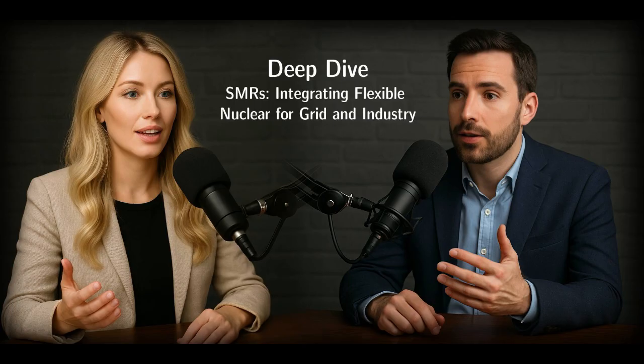Okay, so beyond just following load up and down, how do small modular reactors help with more advanced grid services, like frequency regulation and voltage support? Right, so for frequency regulation, they offer immediate governor response, that's primary frequency response, the instant reaction to a frequency drop, and they can participate fully in secondary response through automatic generation control. How much adjustment can they provide there? Typically a plus or minus 5% power adjustment capability specifically for frequency regulation, with sub-second response for that primary action and seconds for the secondary.